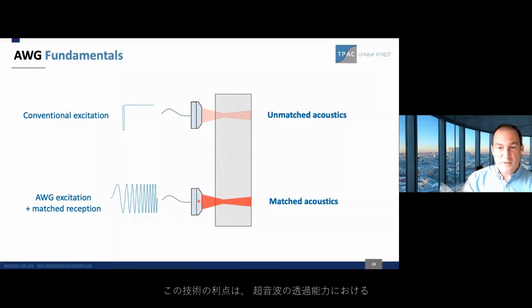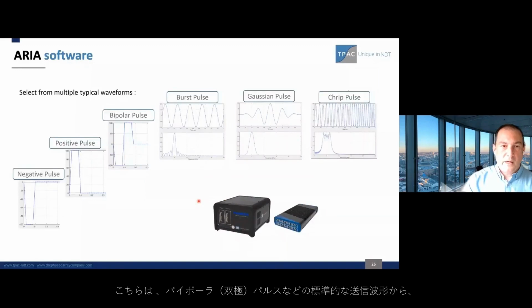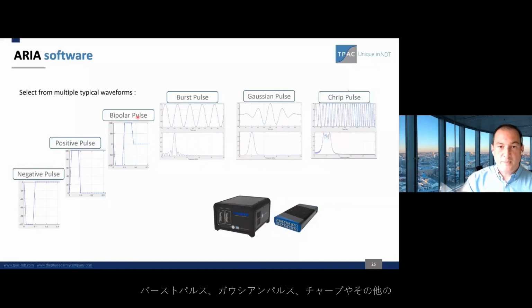The main benefit of this technology is that we can improve the signal to noise ratio and the penetration capability of ultrasound. This is how we program different types of arbitrary waves, going from the standard ones like negative, positive, bipolar pulse, to burst pulses, Gaussian, chirp, or whatever wave shape matches the probe and the material better.